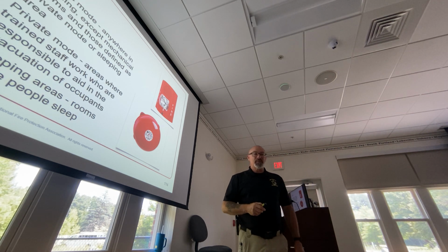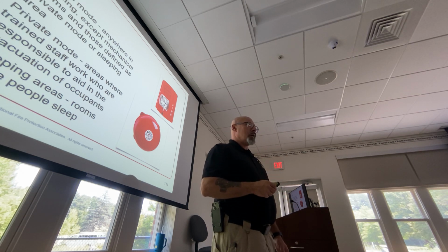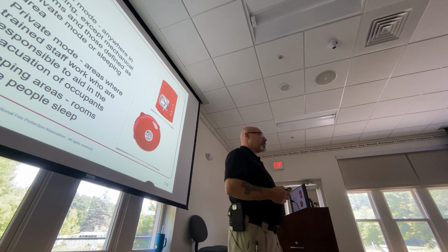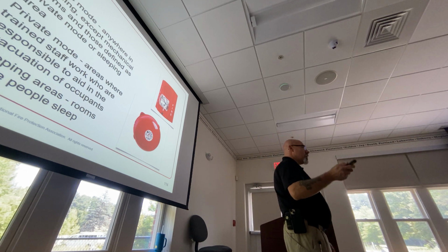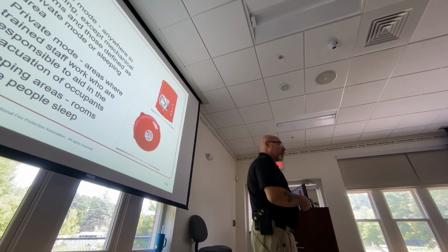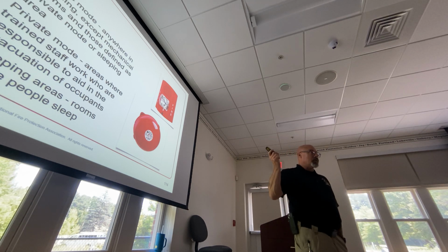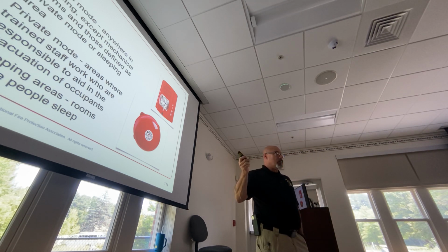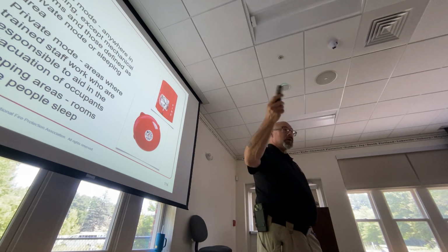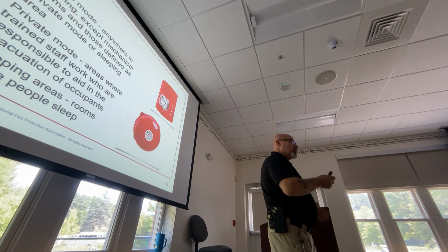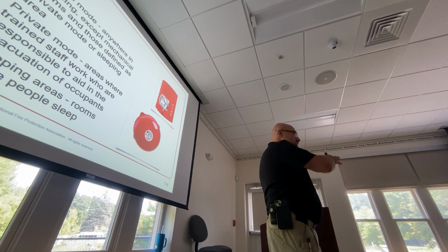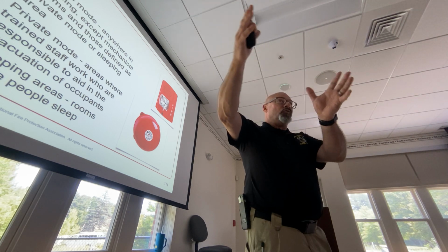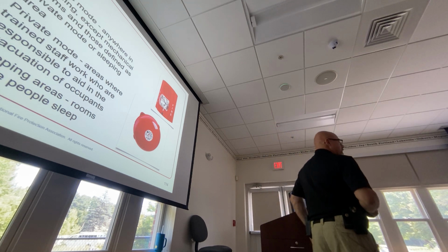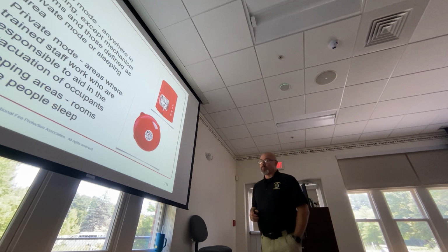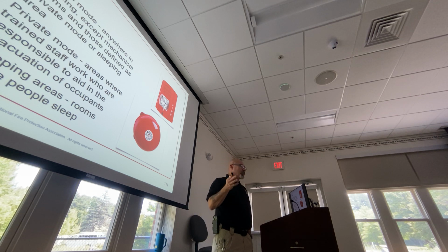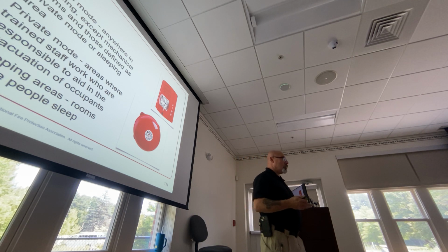How many people have been at the hospital and hear ding, code red? That's a fire alarm. Okay? That's not for you to jump out of bed and go running out of the building. That's to notify all of the employees that there's a fire alarm occurring, and maybe we need to get all the doors closed. Maybe we need to evacuate all of the occupants from this smoke compartment to another safer smoke compartment. That is what we call private mode. Does not necessarily go into a full alarm like we're normally used to hearing.